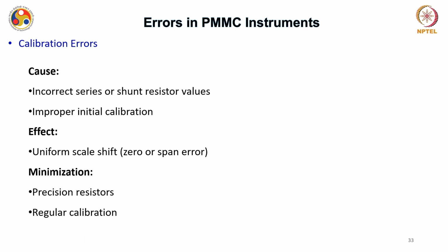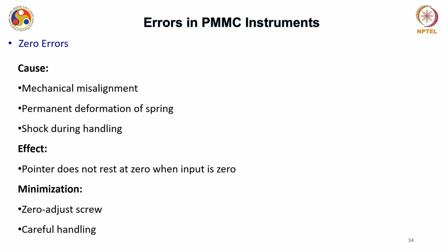So, there are then other errors like calibration errors, where the cause is incorrect series or shunt resistor values, or improper initial calibration of the device. Okay, and there can be several effects, particularly a uniform scale shift, which is very difficult to find. Okay, this can again be minimized by using precision resistors, or by doing regular calibration of the instrument. Okay. Then zero errors are something these PMMC instruments are susceptible to.